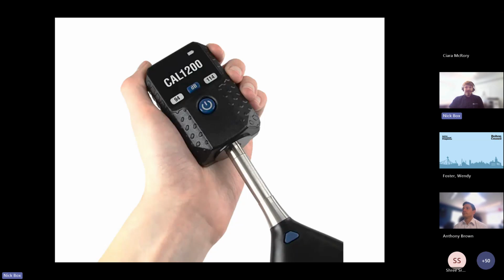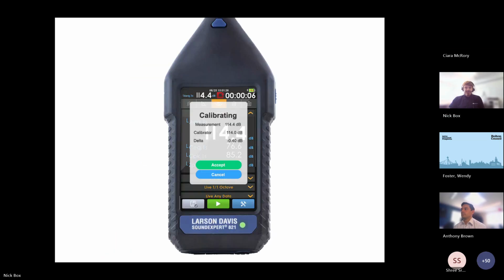As mentioned previously, the calibration function is automatic on the Sound Expert. This process is easy: insert the microphone into your calibrator and turn the calibrator on. A window will open automatically on the Sound Expert. Once the level on the calibrator has stabilized, you'll get a notification and can press accept. Once you press accept, the meter will log the calibration history and the sensitivity of the microphone, and you're free to use the instrument as you wish.